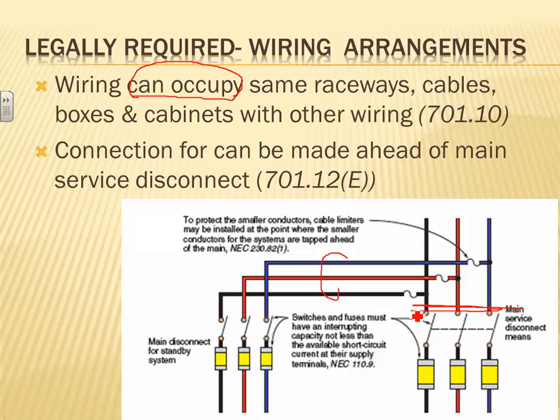Number two, think of survivability of this system. You have a legally required standby system for a reason, because you care about the power, so important, right? So if you mix them with another circuit, you have compromised the integrity of these branch circuits, meaning if there's a short circuit in the normal, it could take with it the legally required standby system. So the survivability of the system and the ease of maintenance for 50 years.